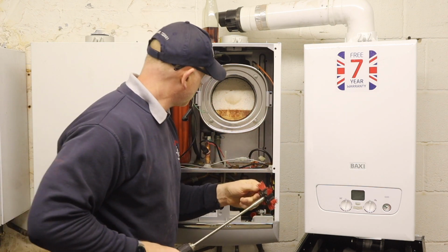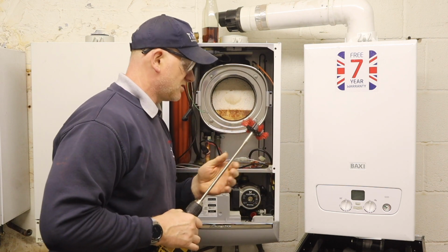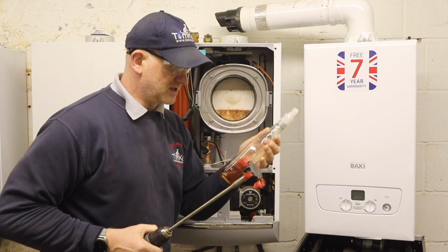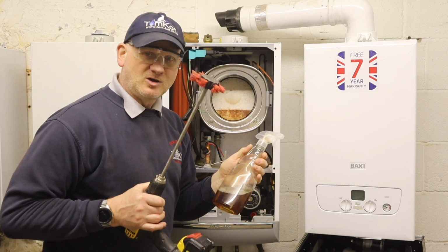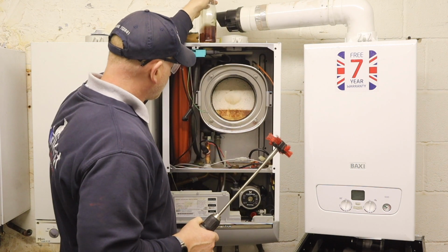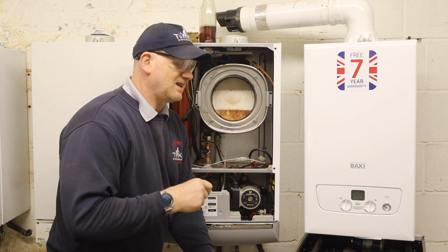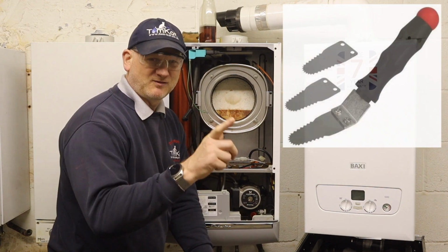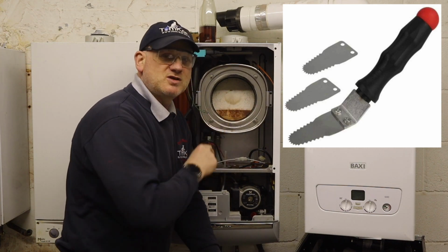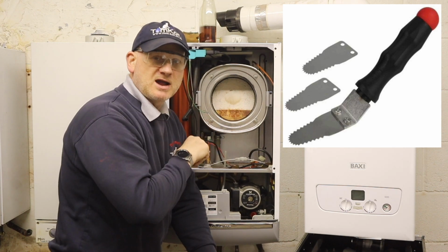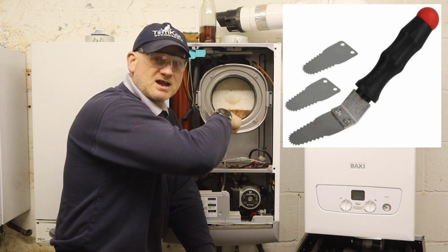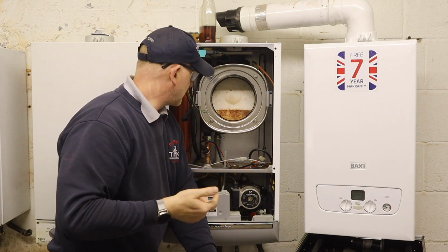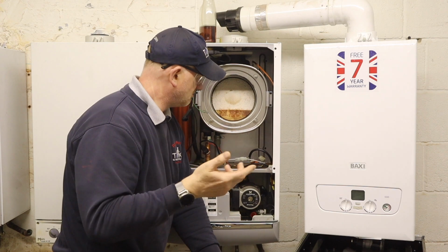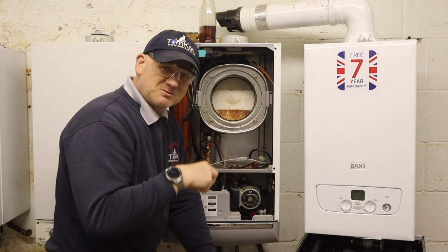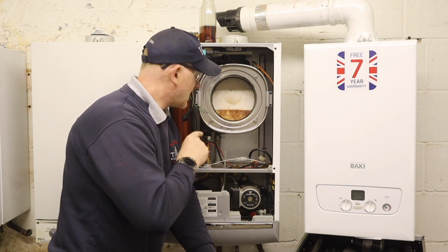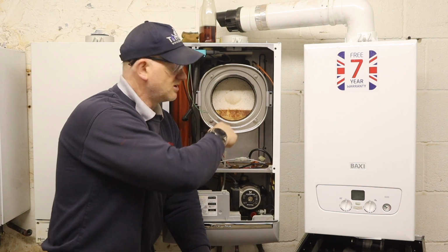You could spend ages doing this, but I just spent a few minutes. There are two different ways of cleaning: we can either use the vinegar or this brush. Also, you can buy little spatulas - like a flat knife - where you can get in between the pipes going around the heat exchanger to clean the gaps down there. A plastic one would be better than a metal one, but one of the boiler manufacturers actually makes one for you. So that's another good way of cleaning the heat exchanger.